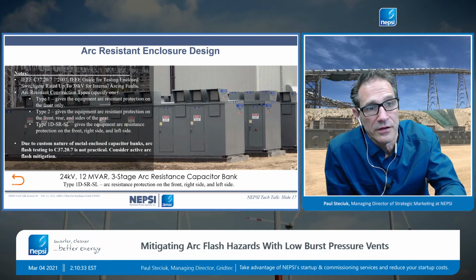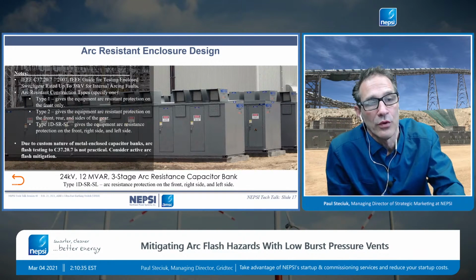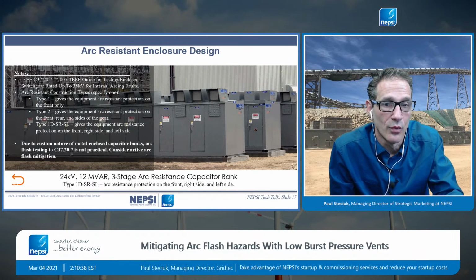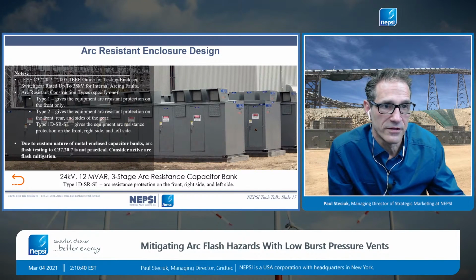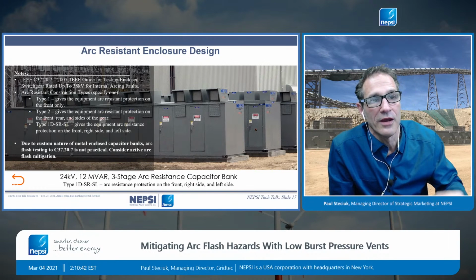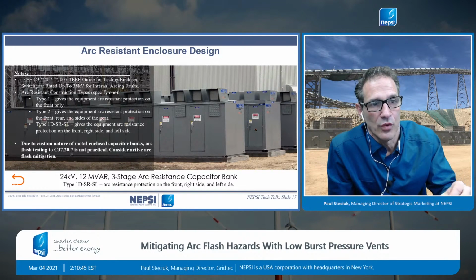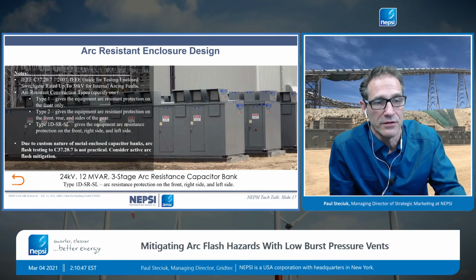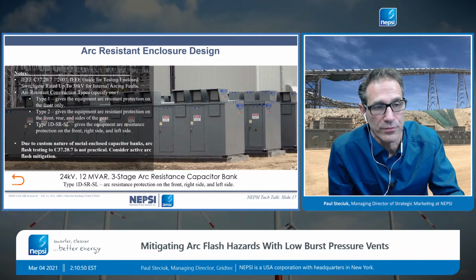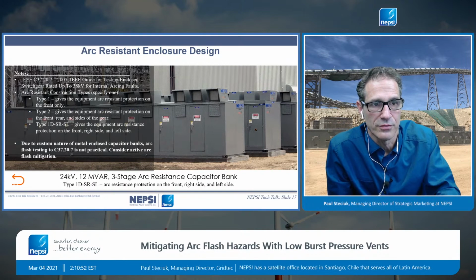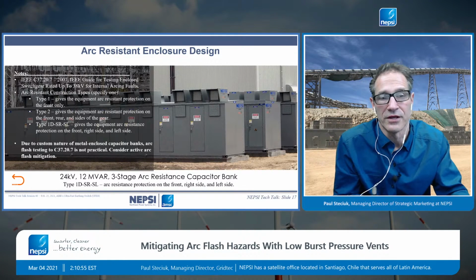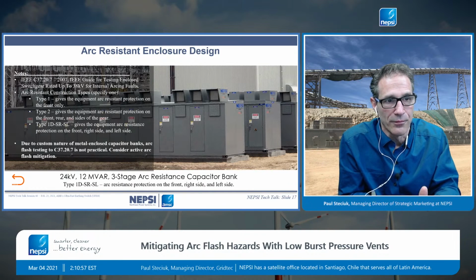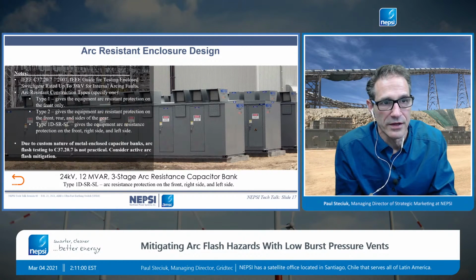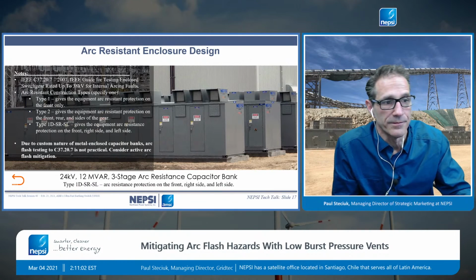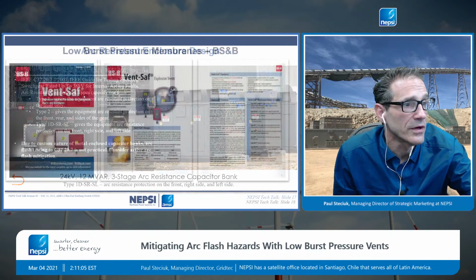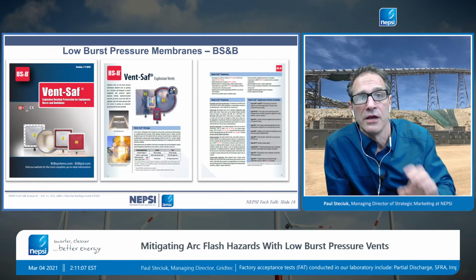So if we can't do the test or the customer's not willing to pay for the test, well, what can we do? One of those things we can do is we can put these low burst vents in. That's a way to try to get to a piece of equipment that is safe. We can also insulate the bus bar, increase the BIL, put faster protection in, put the ABB ultra-fast earthing switch in. There's a lot of other things we can do, and that's what we do at NEPSI, is we're trying to approach this certified piece of equipment without actually certifying it. So anyways, we'll continue here. This is what we're using.